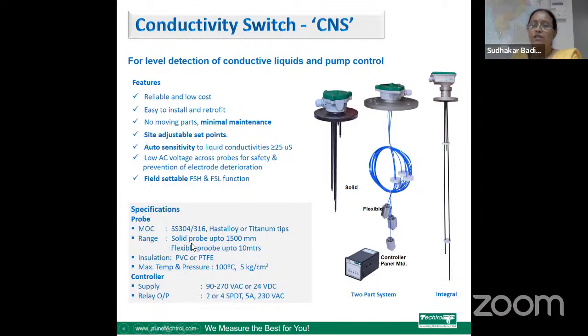The electrodes are available as a solid probe up to 1500 mm and a flexible probe up to 10 meters. The insulation on these electrodes will be PVC or PTFE. The switch is suitable up to 100 degrees Celsius and 5 kg per centimeter square pressure. The supply for this controller is 90 to 270 volt AC or 24 volt DC, and the output of this switch will be relay output, which is rated for 5 ampere at 250 volt AC.